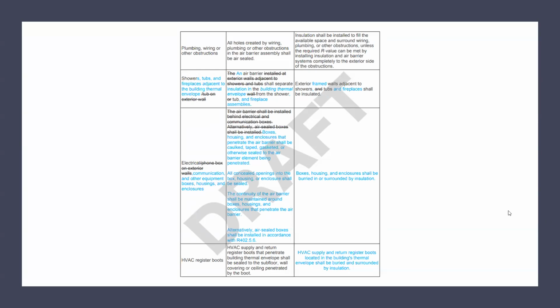And also, it says all concealed openings into those boxes, housings, and enclosures shall be sealed. So if you have a communication box, like an internet provider gives, the boxes that have all the holes in the back of it, those need to be sealed. But if you seal them, you're voiding the warranty of the equipment because you're not allowing air movement through the box. I.e., there's a reason why you should not be putting it on an exterior wall and or thermal envelope. You must put it or should put it on an interior wall that now you don't have to follow those requirements.